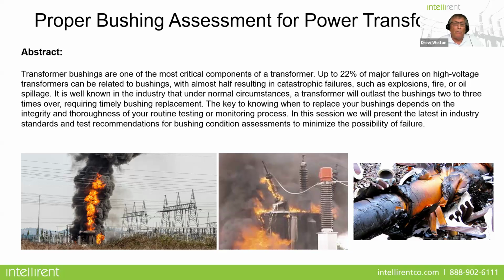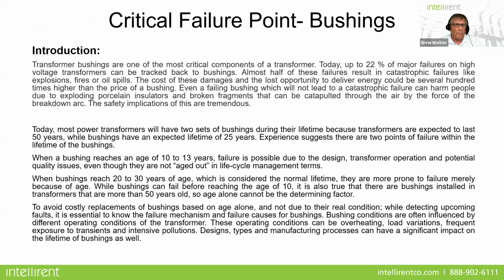These are explosions, fires, or oil spillage. And it's well known in the industry that a transformer itself will outlast the bushings at least 2 to 3 times over. The key to not having these catastrophic failures is to know when to replace the bushings. And that depends on a number of different things. The integrity and the thoroughness of your routine testing or monitoring process is very important. But what we do know is that, based on certain criteria, there's no common age theory or theoretical age relative to when we can expect a failure.